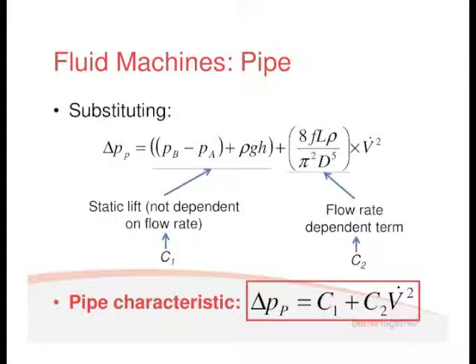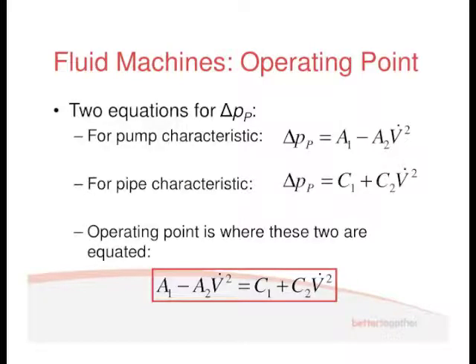So we've got a pump characteristic, which is the A terms. We've got a pipe characteristic, which is the C terms. And you can match them together. We've got two equations for delta PP. For pump characteristic: delta PP = A1 minus A2 V dot squared. For pipe characteristic, you've got delta PP = C1 plus C2 V dot squared. You put them together, you end up with this equation. So this is due to the pipe, this is due to the pump.